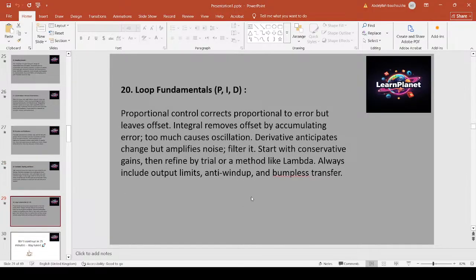Loop fundamentals. Proportional, integral, derivative: PID. Proportional control corrects proportionally to error but leaves offset. Integral removes offset by accumulating errors, but too much causes oscillation. Derivative anticipates change but amplifies noise, so filter it. Start with conservative gains, then refine by trial or a method like lambda. Always include output limits, anti-windup, and bumpless transfer.